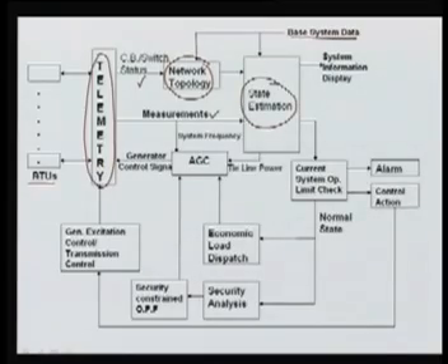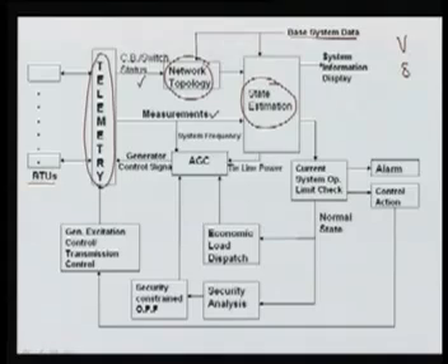State estimation is slightly different from the power flow study, and you know the states of the power system are nothing but the voltage and the angle at all the buses. This angle is not a power factor angle; it is the bus voltage angle, and V is the magnitude of the bus voltages. With the help of these two pieces of information, at each bus we can determine all the power system quantities, such as the real power flow and the reactive power flow, and we can also determine the power losses, that is, the real power loss and at the same time the reactive power loss as well. That's why we call them the states of the power system.